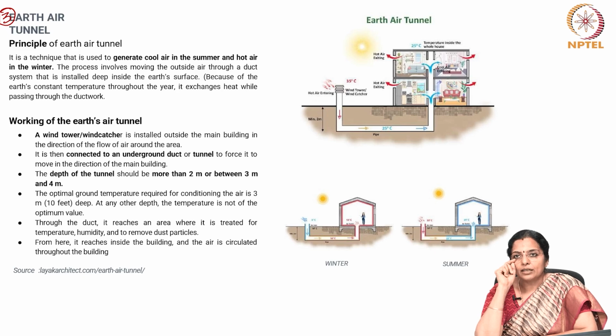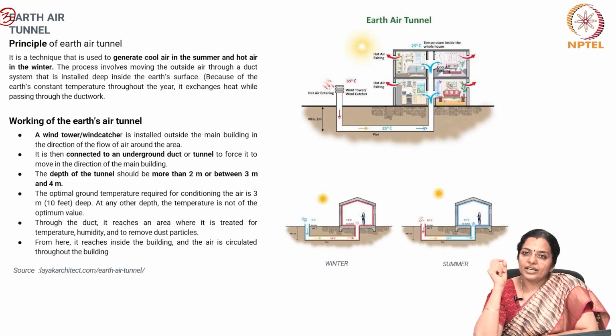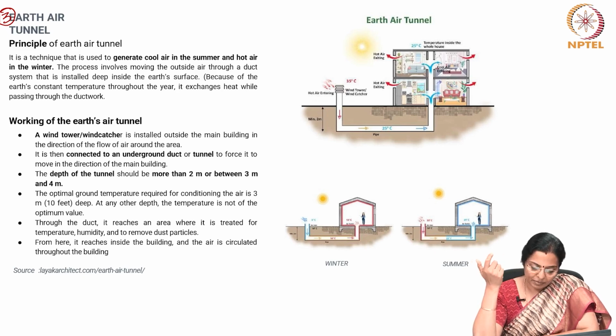The depth of the tunnel should be more than 2 meters or between 3 meters and 4 meters. The optimal ground temperature required for conditioning the air is 3 meters below the ground. At any other depth, the temperature is not of the optimum value. Through the duct, it reaches an area where it is treated for temperature, humidity, and to remove dust particles. From here, it reaches inside the building and the air is circulated throughout the building.